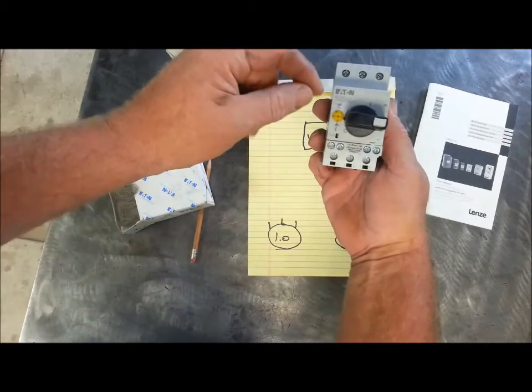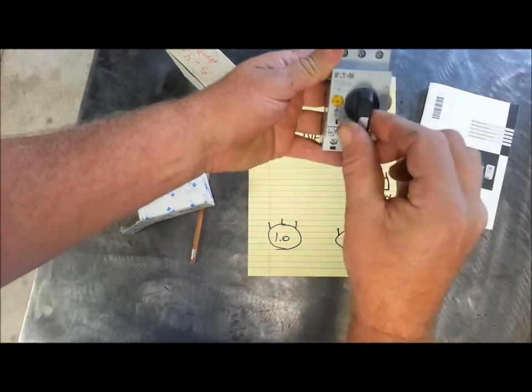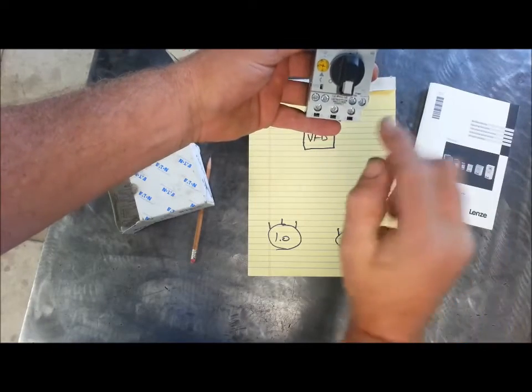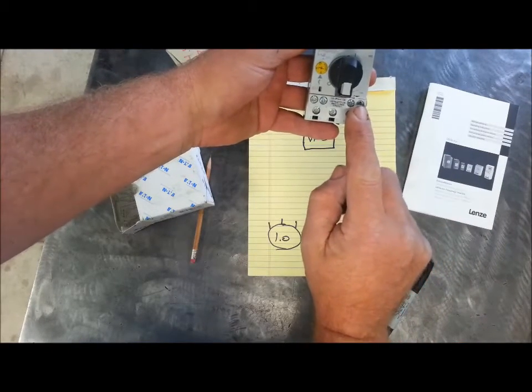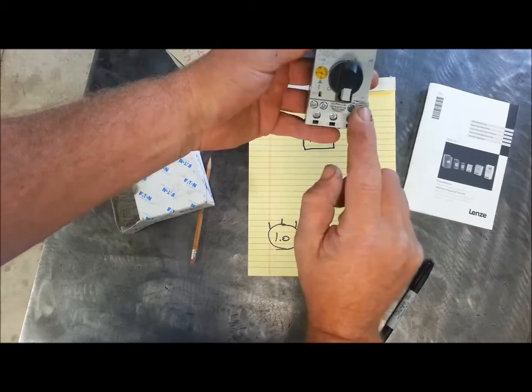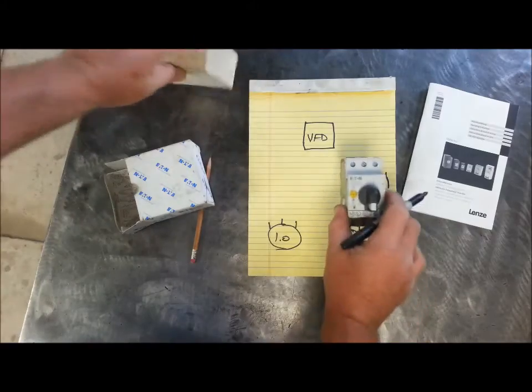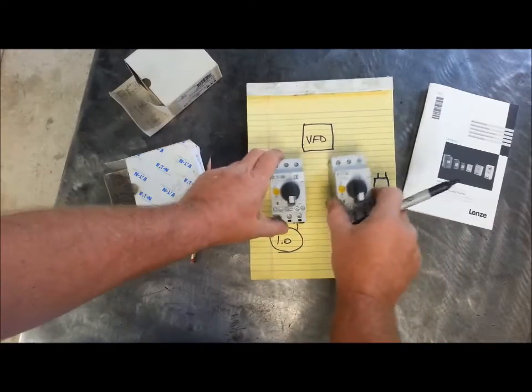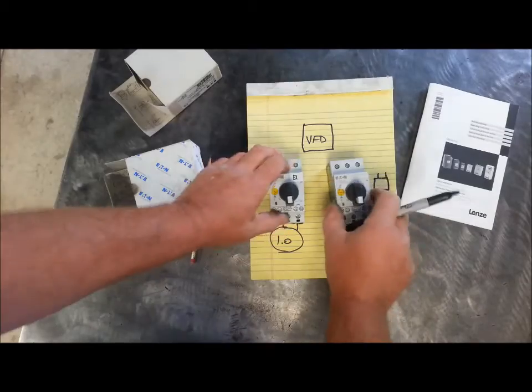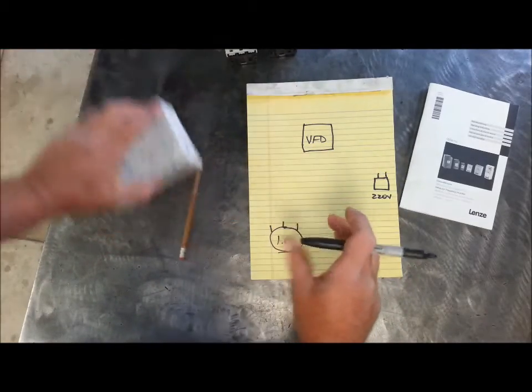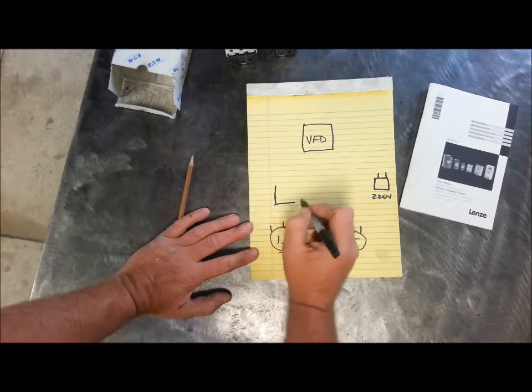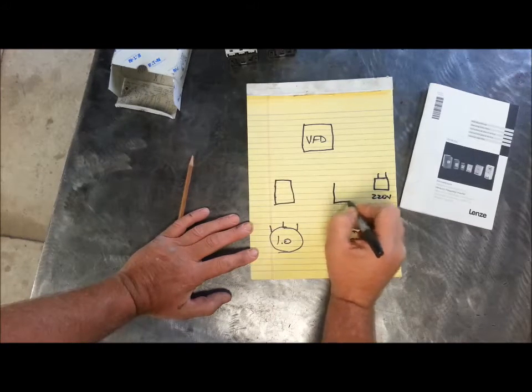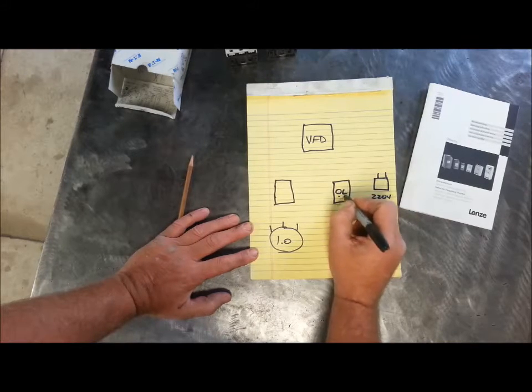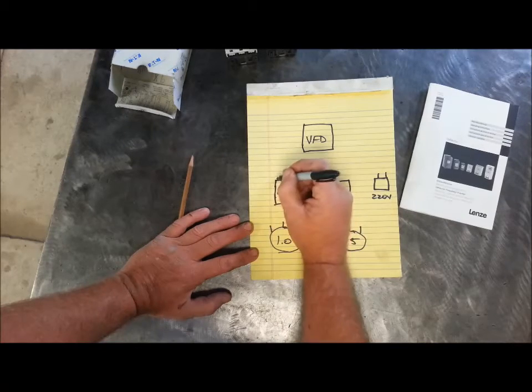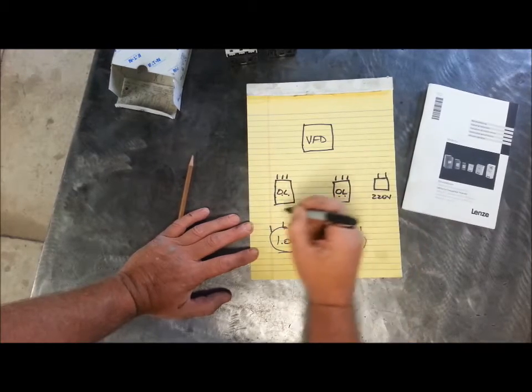And we're going to wire these to the normally closed. And when I say normally closed, when this thing is in the run position and the three phases going through are closed, the switch gear is also closed, the auxiliary switch gear. And this is just pilot duty. And we're going to get to the pilot of that later. So we have two of these. There's going to be one for each motor to protect the motors individually. All right, so we're going to draw these on the drawing. And those are considered motor protection overload blocks. We're just going to call them overloads. And I'm just going to put OL on there. And those are three in and three out.